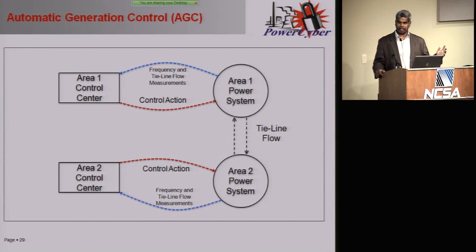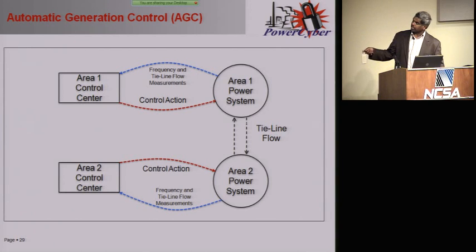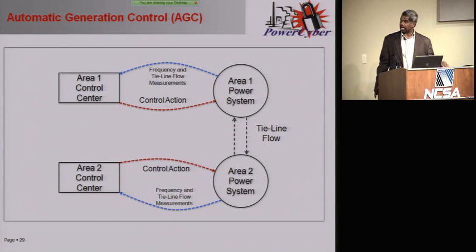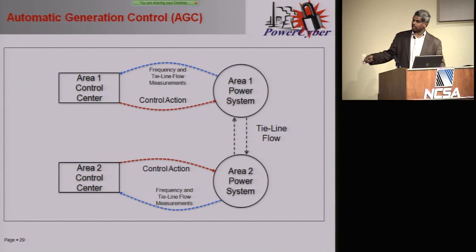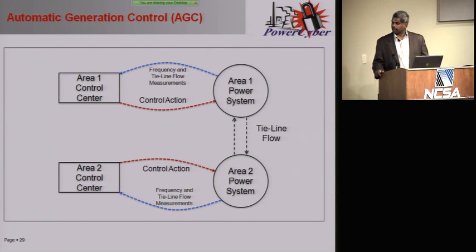This is basically scheduled interchange between control areas, commonly agreed upon. What is being measured by sensing or communication is frequency and tie line measurement. These are two important measurements for the control algorithm: what is the frequency of this control area, and what is the tie line flow going this way? Similarly, we measure the tie line flow and frequency on the other side. Based on these measurements, the algorithm computes what control action is needed, whether generation has to be increased or decreased, ramped up or down.